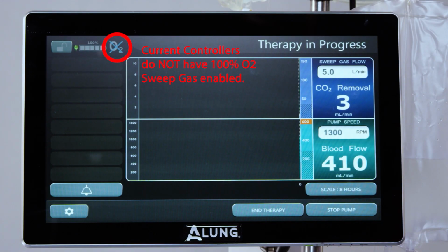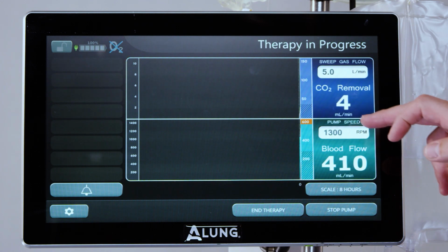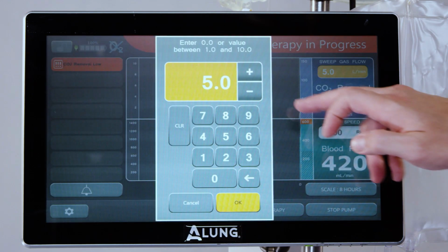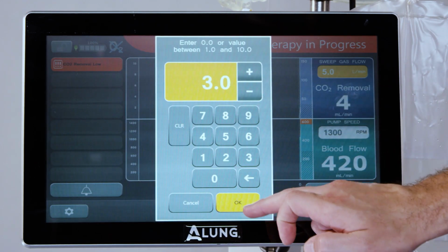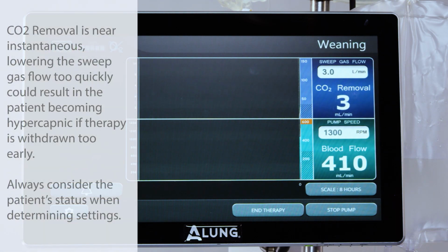Weaning from therapy is done by progressively reducing the amount of CO2 removal while closely monitoring the patient. To reduce CO2 removal, reduce the sweep gas flow rate. After reducing the sweep gas flow rate, the new CO2 removal rate will display on the screen after approximately 2 minutes. The sweep gas flow rate can eventually be reduced to 0 while the blood flow is maintained to evaluate the patient's response to withdrawing therapy.